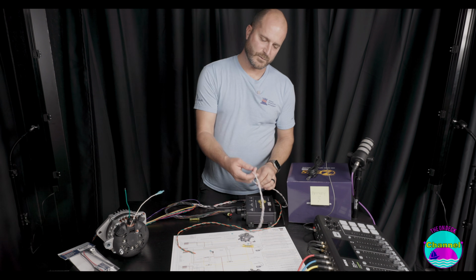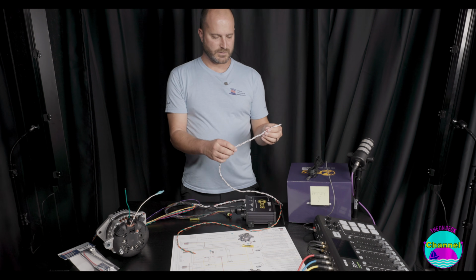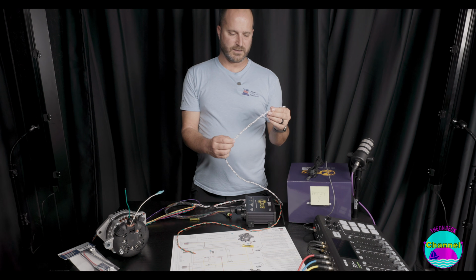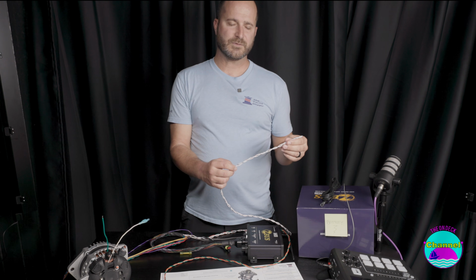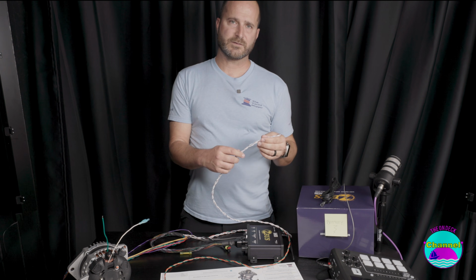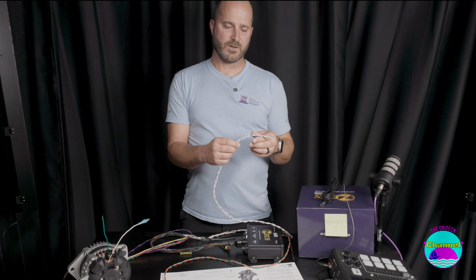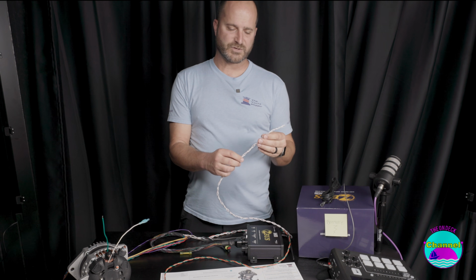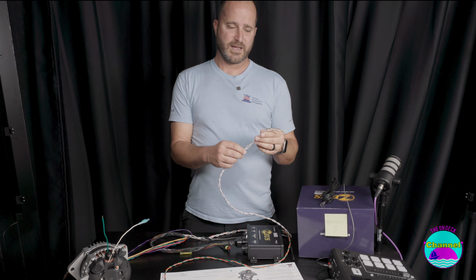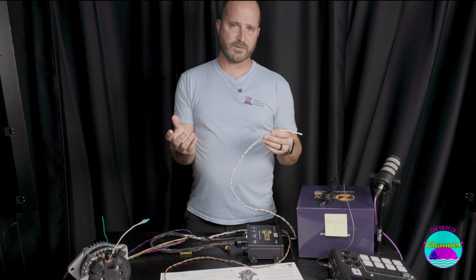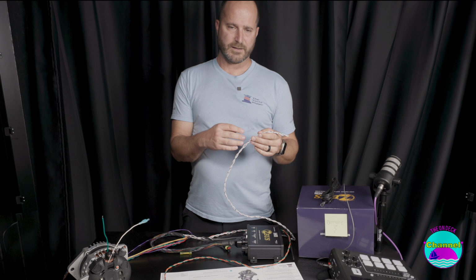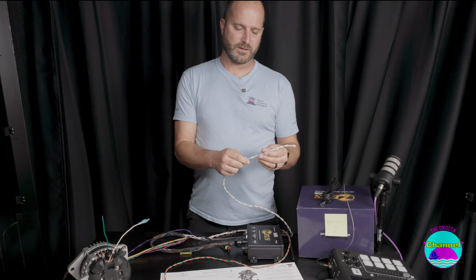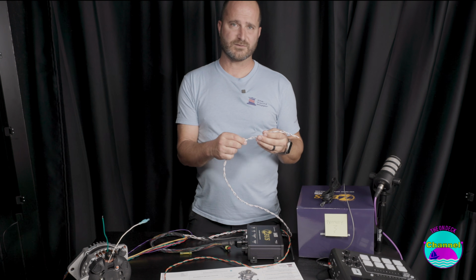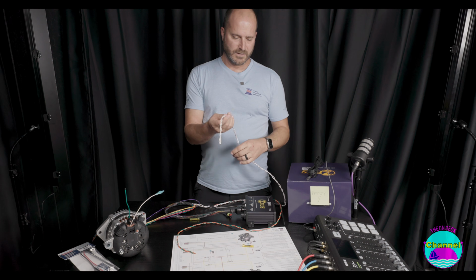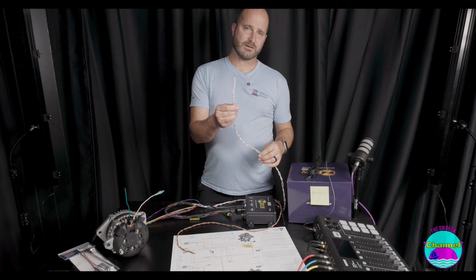With this twisted pair, just for explanation's sake, it helps combat interference within the wires, because we're measuring very small voltages and there could be interference, say from a VHF communication cable or other sources. A twisted pair can help shield against that. For a shunt it's definitely a requirement.